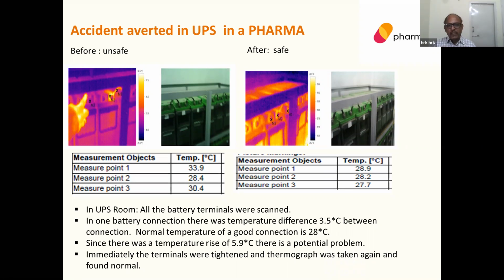So we immediately took corrective action and tightened the terminals. On the left side you see the terminal difference from 30 to 33.9, more than a 3 degree rise. After the corrective action of tightening the terminals and redoing the thermography, we found almost a 1 or 2 degree difference. This is what we can find out, because if it goes unchecked, it can result in sparking and lead to a failure.